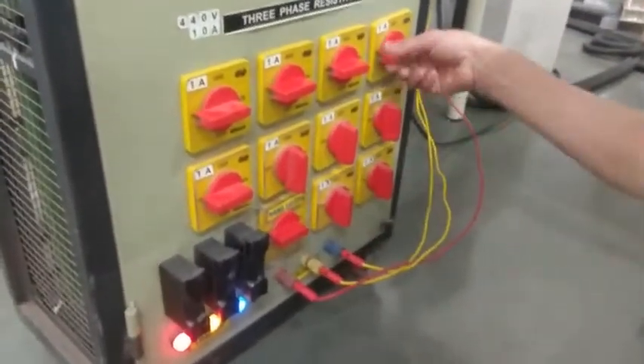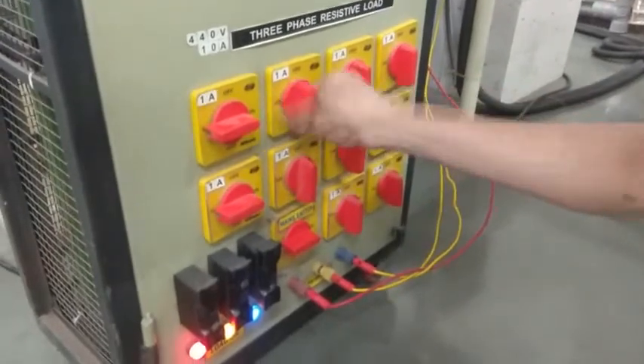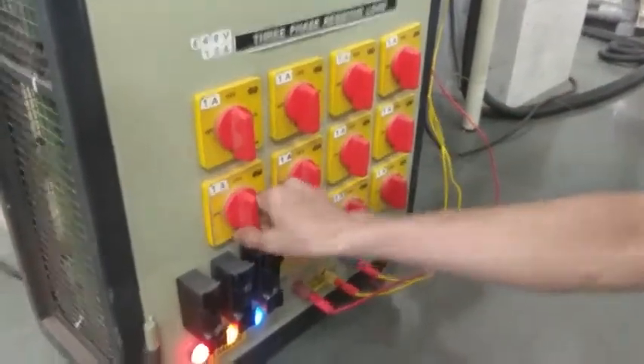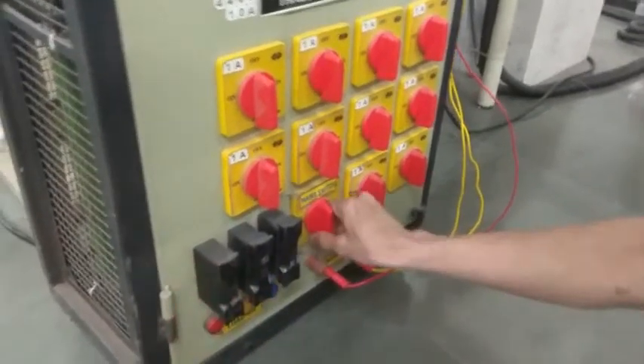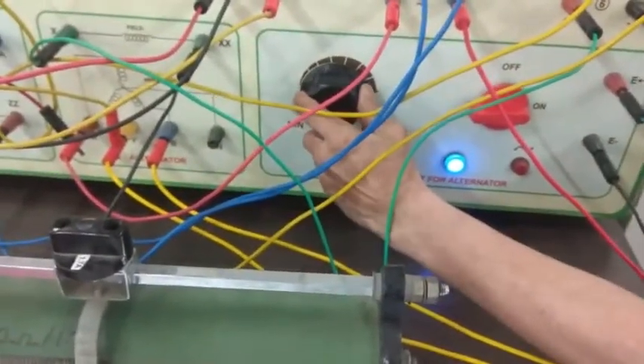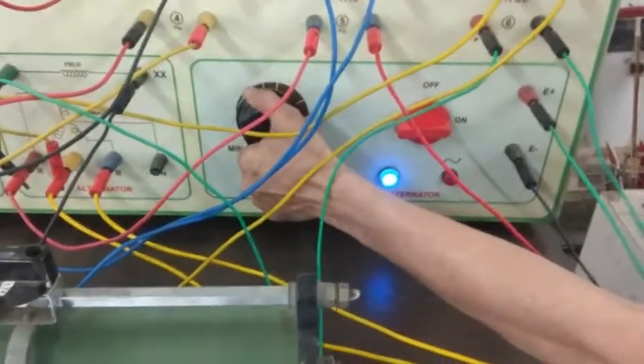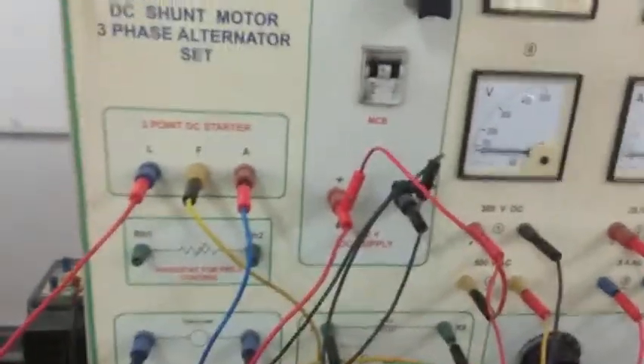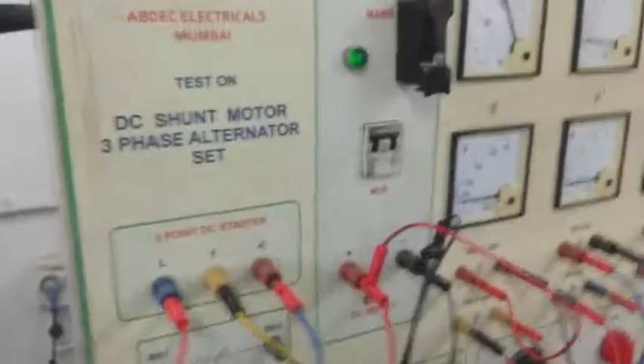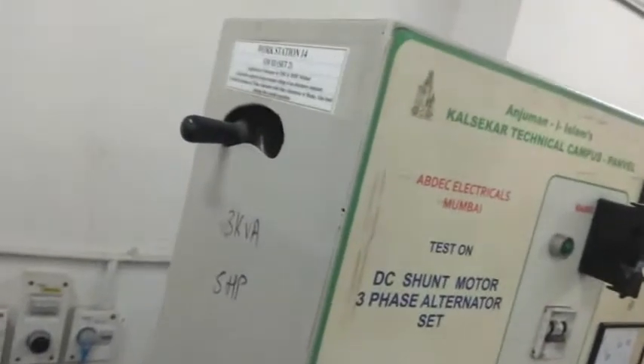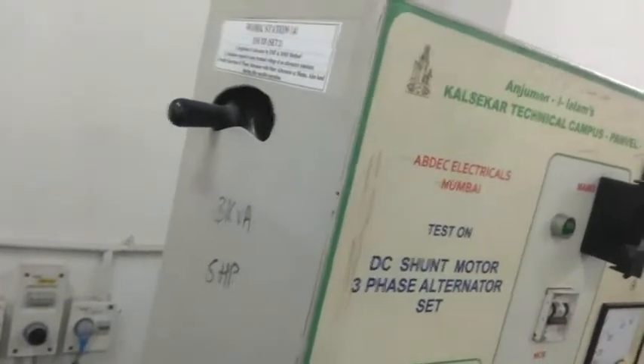Now we will switch off the load bank. We are switching off the load bank. All the load banks should be in the off position. Now the load bank is off. Now we will minimize the field excitation unit and switch off the excitation unit. Then we will switch off the supply. See, when we switch off the supply, the starter handle goes back to its original position.